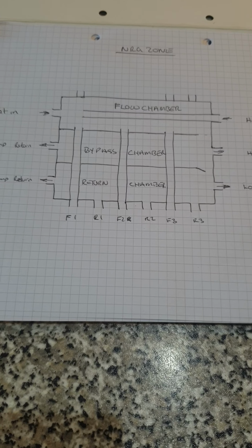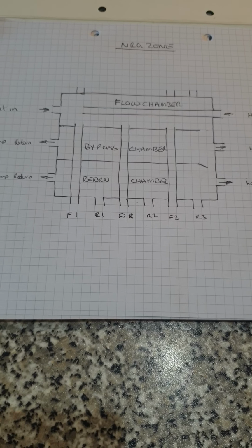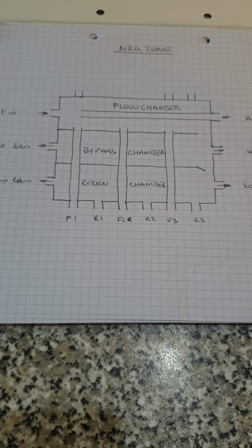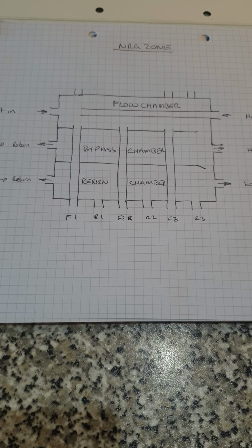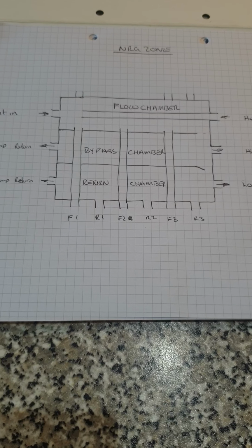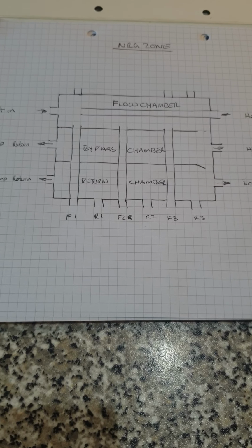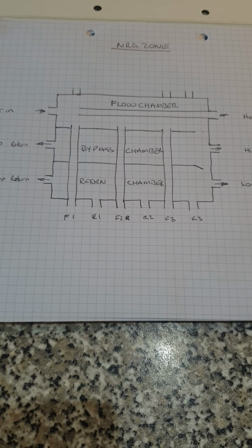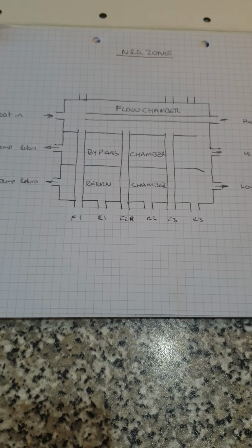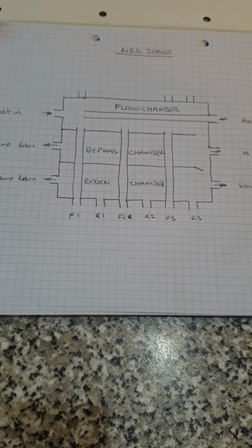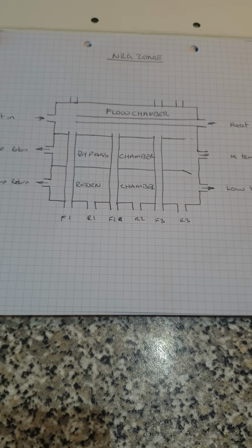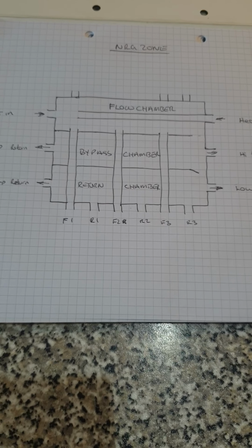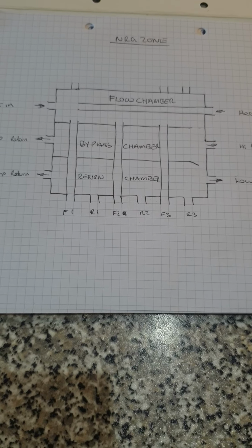Plus, just about every time we do a post about using hydraulic separation to satisfy the differential flow requirements when applying a low temperature gas boiler to a system with a mixture of radiators and underfloor, or even just a system with just underfloor heating on it, we discuss the need for hydraulic separation. This is posted up as being a smarter and better option, and I've been suggesting that this isn't the case for a while.